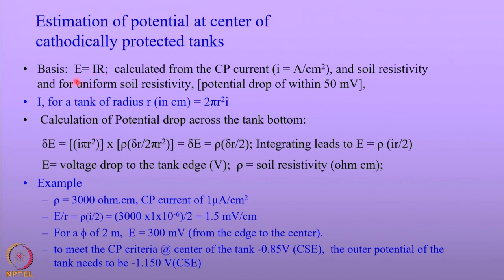We can get this potential value provided we can calculate the current required for protecting the structure and the resistance offered by the soil between two locations. The current density required for cathodic protection can be either calculated or measured, so the current density is known. The soil resistivity is also known and we assume the soil is of uniform chemistry, so the soil resistivity across the bottom of the tank is quite uniform.